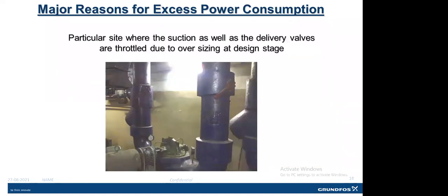And what happens? We need to operate the pump by throttling the valves. These are particular sites where the pump suction as well as delivery valves were throttled due to oversizing at the design stage. This pump was designed at a much higher head than the actual head required. So we need to operate the pump by throttling the valve, and by throttling the valves we are creating artificial head on the pump, thereby increasing the power consumption of the pump.